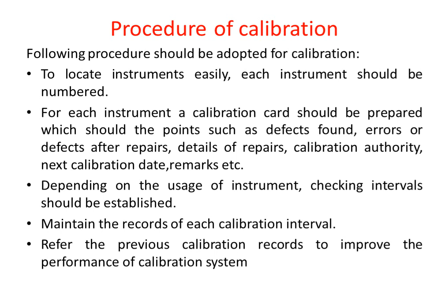Let us see the procedure of calibration. Following procedure should be adopted for calibration. To locate the instruments easily, each instrument should be numbered. For each instrument, a calibration card should be prepared, which should contain the following points such as defects found, errors or defects after repairs, details of repairs, calibration authority, next calibration date, remarks, etc. Depending on the usage of the instrument, checking intervals should be established. Then maintain the records of each calibration interval. Refer the previous calibration records to improve the performance of calibration system. So all these are the points included in the procedure of calibration which need to be followed.